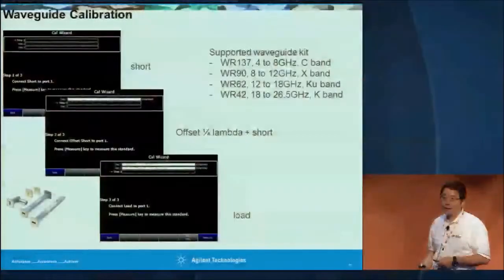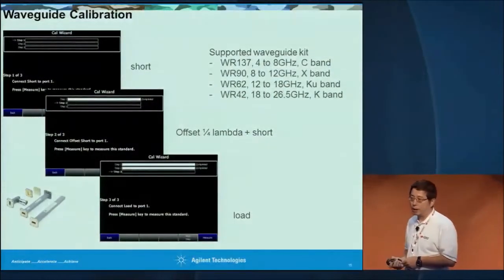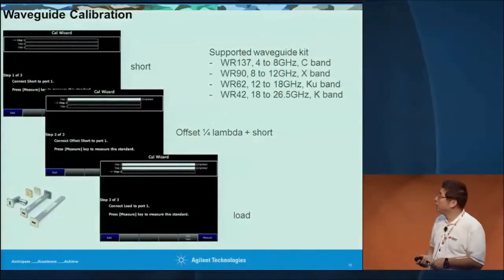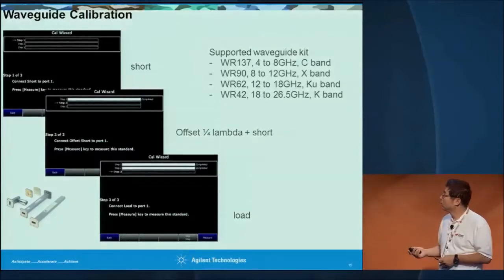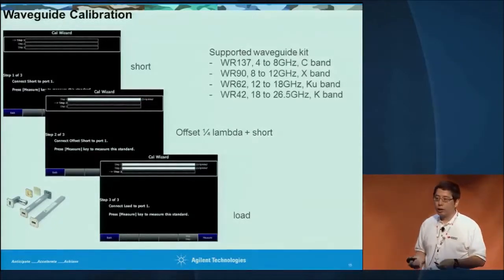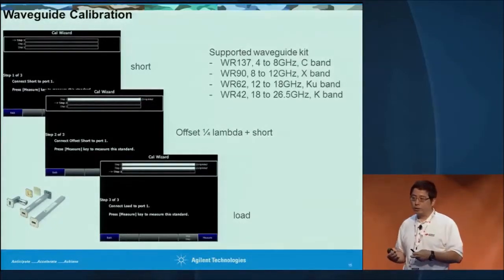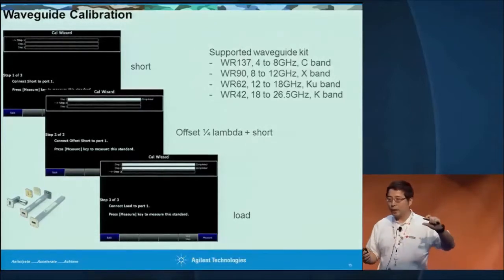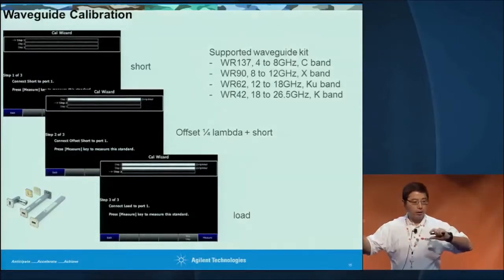This is a quick demonstration about waveguide calibration. You can also define your own calibration kit. In some situations you may have a different waveguide flange at each port — you can define your own calibration to make those measurements. The bottom line is we want to make accurate measurements in the field.